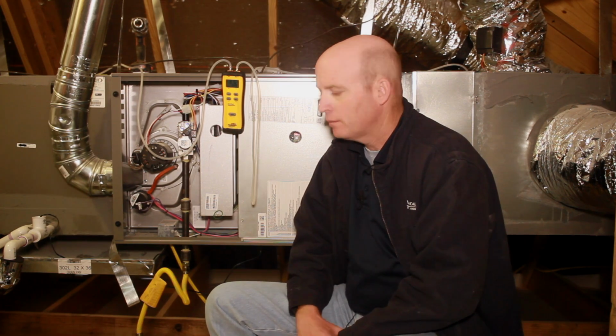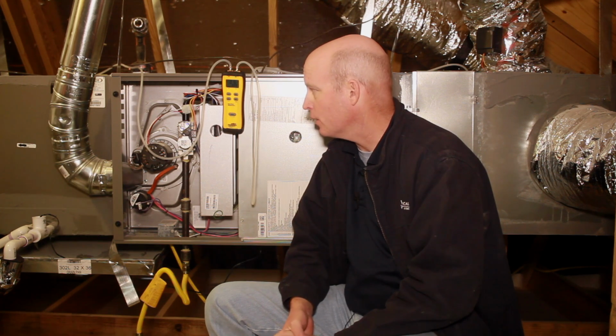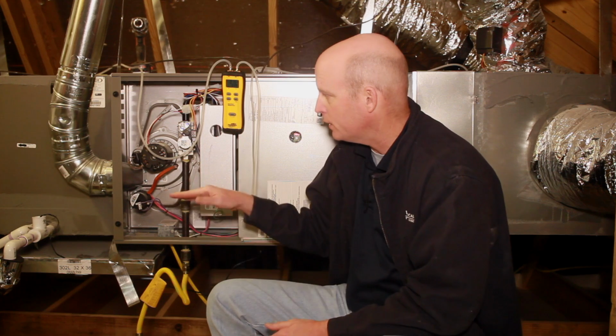Let's look at air conditioning tonnages. Every ton of air conditioning requires approximately 400 CFM of air. With 1700 CFM of air going through this, we could handle a little more than a 4-ton unit. If this were a 5-ton unit, we would be shy on air, and we would have to make adjustments to the blower speed. If this were a 3.5 or a 3-ton air conditioner outside, we would have to make adjustments to lower that CFM.